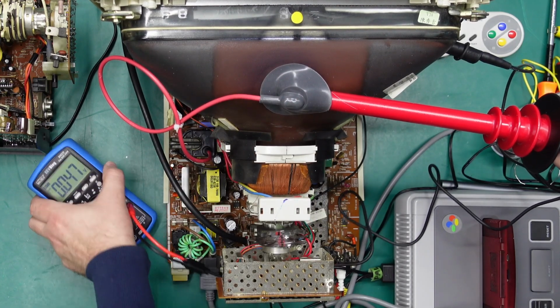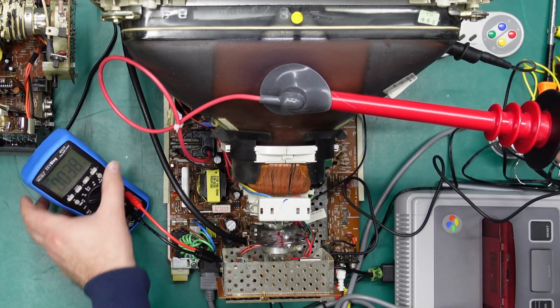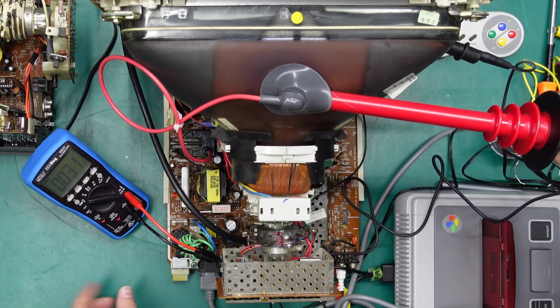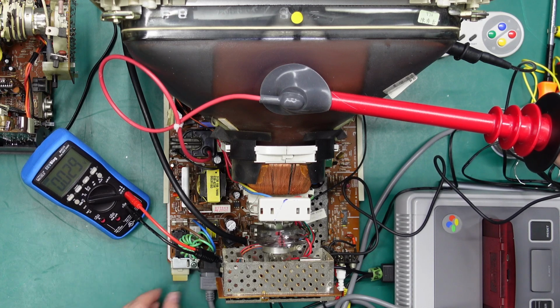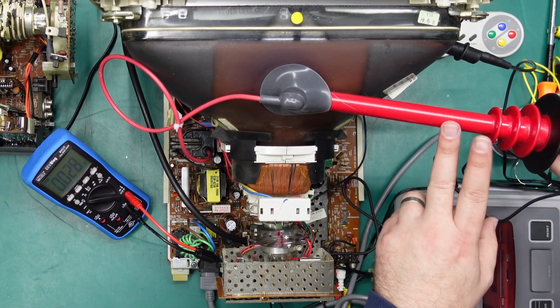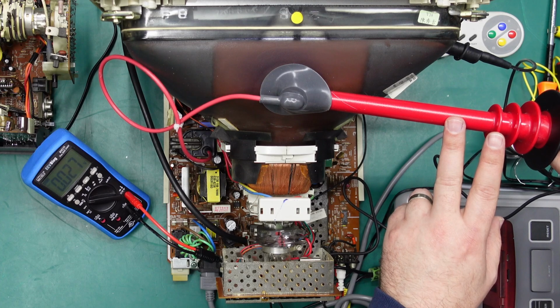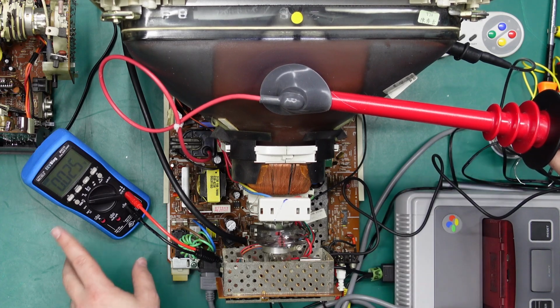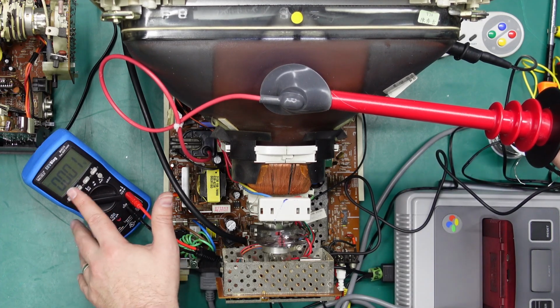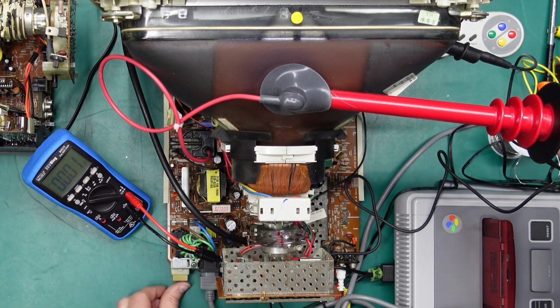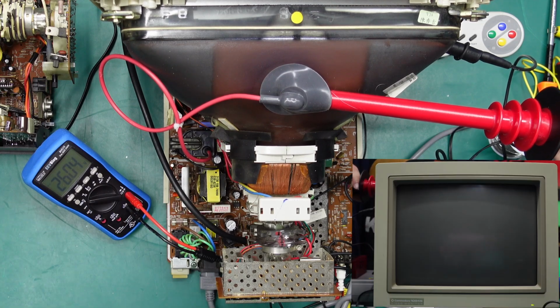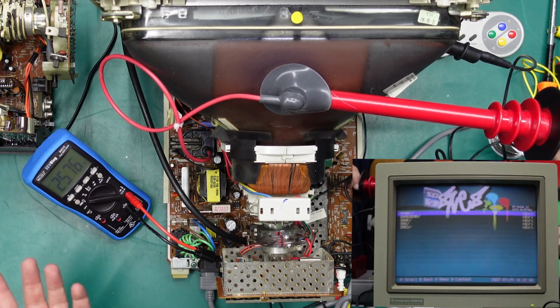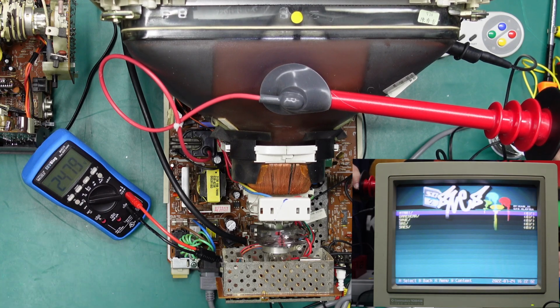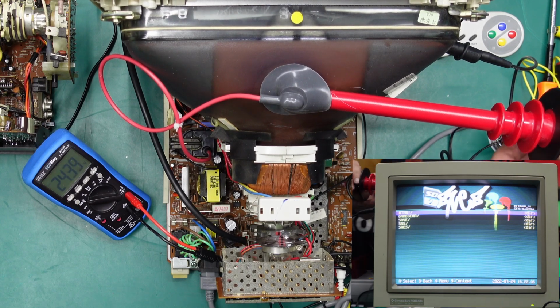So I've got the probe set. The CRT is currently off, so let me set up the multimeter so we can see it. Let's power this on. Now this is a 100x, or is it 1000x? 1000x probe. So the reading that we see on the multimeter here, times that by 1000 to get the actual voltage. So at the moment it's saying 26, so we've got 26 kilovolts thereabouts, and it's quickly dropping down, I guess, as the screen came up.